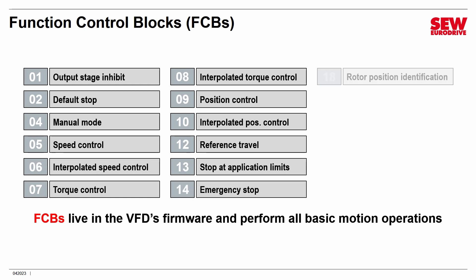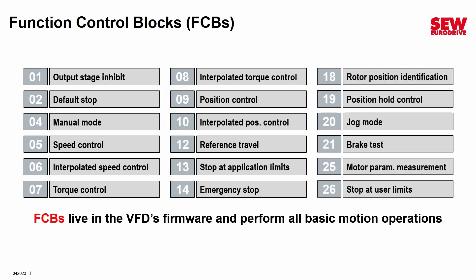The master list isn't actually too large — there are only 18 FCBs at this time. They each have a number, and you'll notice some missing numbers in the list. It goes from 1 to 26, but there are only 18 total, which maybe suggests there will be others at some point. These FCBs live in the VFD's firmware and perform all the basic motion operations. For example, FCB 05 is used for basic speed control, 07 does basic torque control, 20 does jogging, 01 does output stage inhibiting, 02 does default stops, and 04 does manual mode. Each one does a specific basic task that is important in what a VFD does.